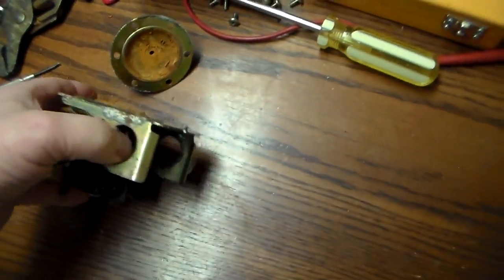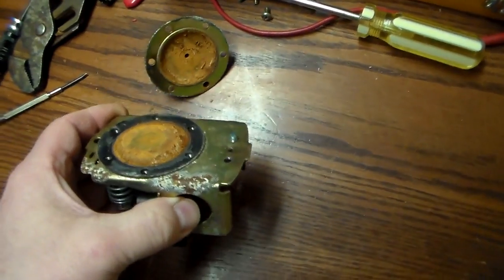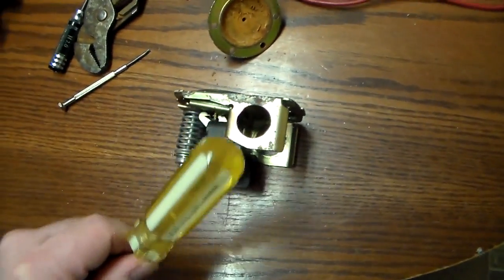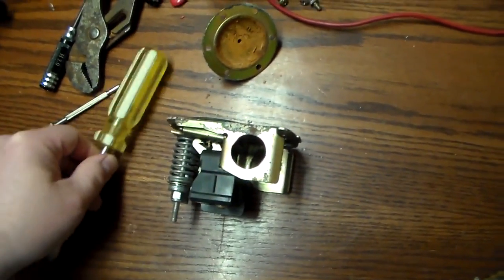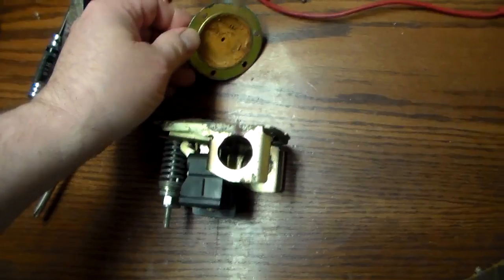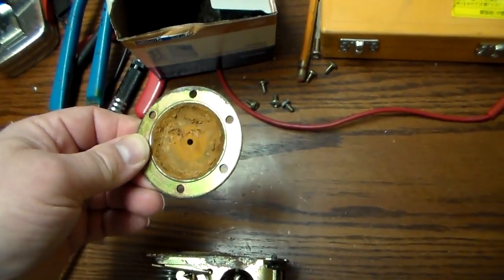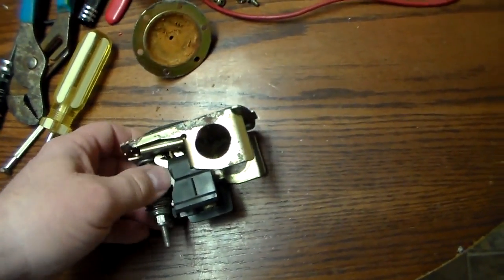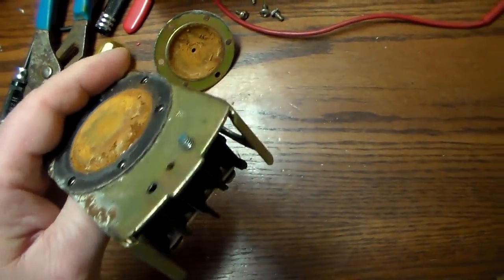I'm going to clean this one up. It was acting up, it was sticking off and I'd have to run down the basement and tap the box with a screwdriver handle. It would work for another two or three weeks and then it would stick off again. Sure enough, there's rust accumulation in there and that just interferes with its ability to function.